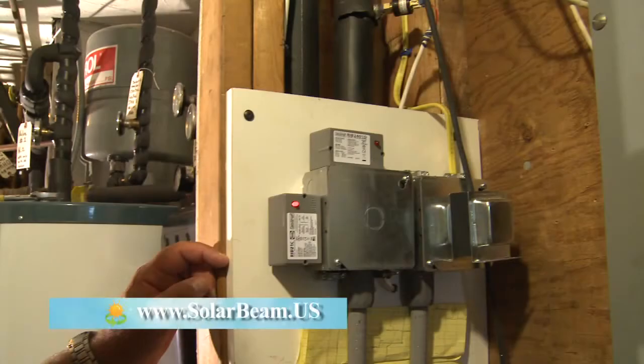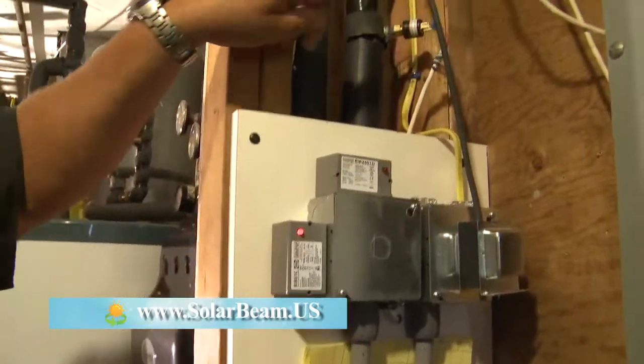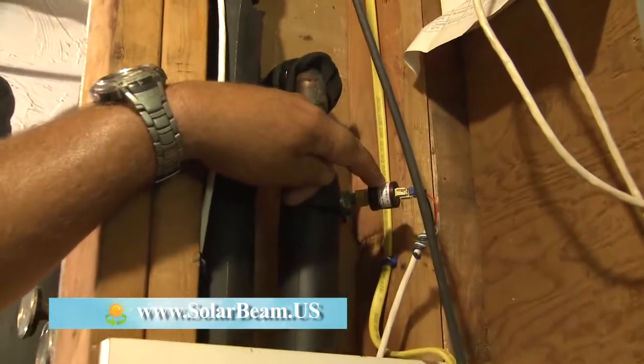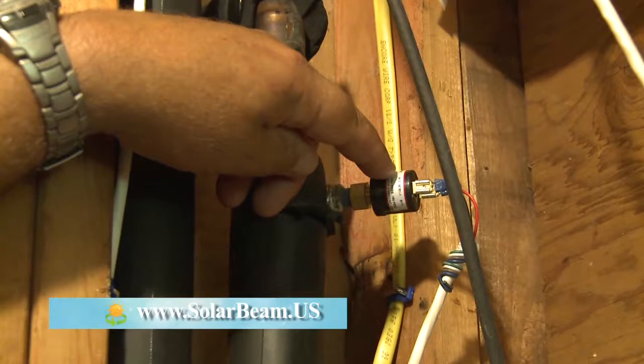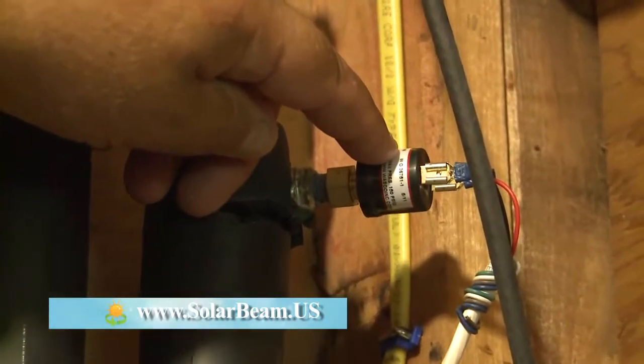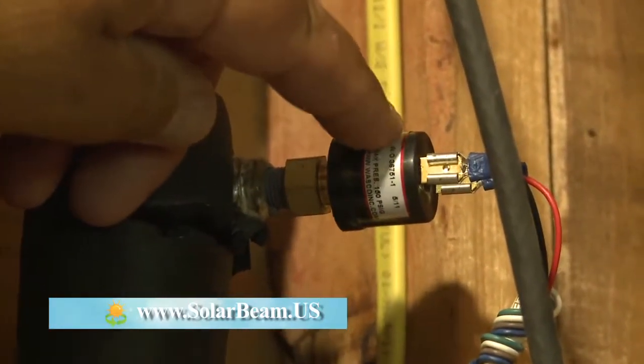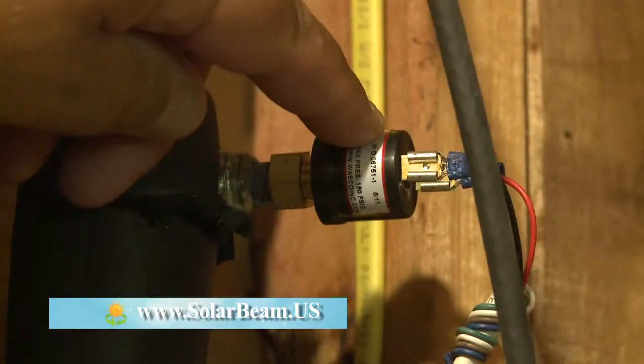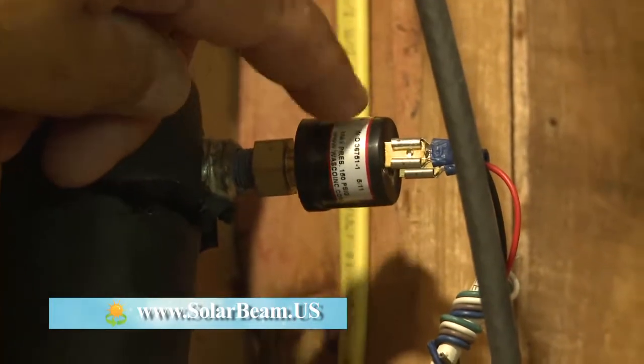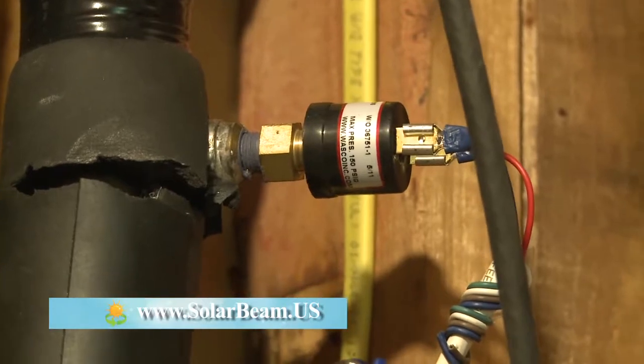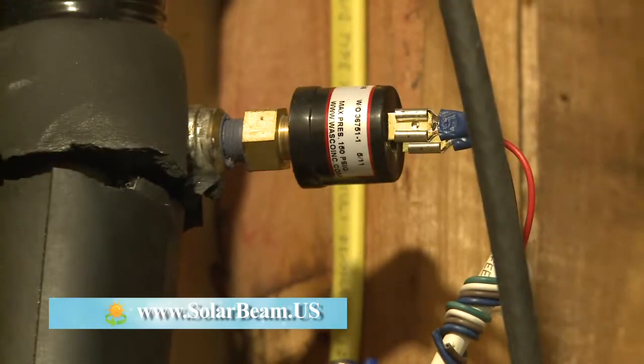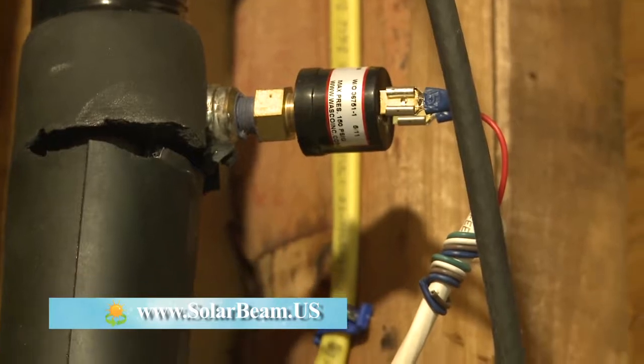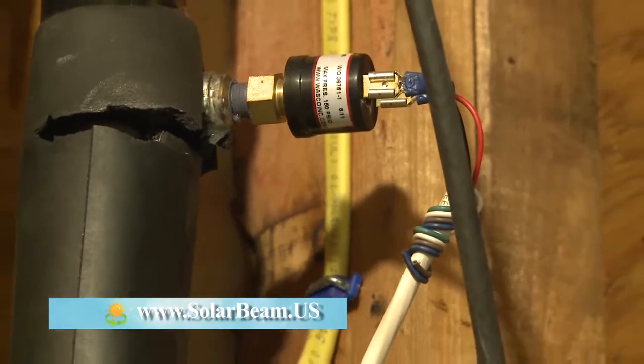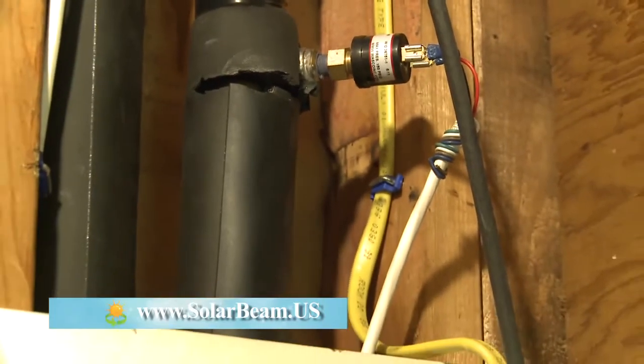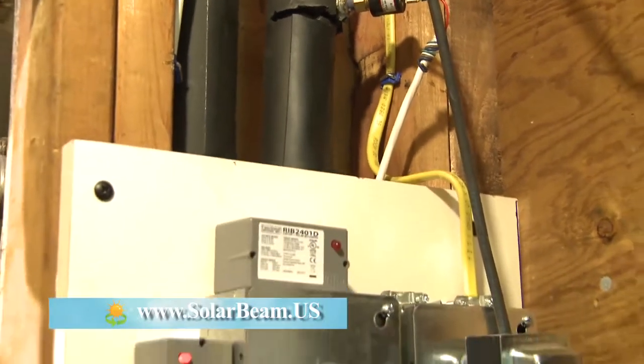There are several safety devices in the SolarBeam to prevent any type of overload or overheating. Right up in this area, this right here is a pressure switch. And if the pressure in the solar loop of the water that's going to and from the solar dish ever goes below a certain pressure, and I think it's set at 6 pounds, the SolarBeam will turn off. This is a pressure switch. We also have temperature sensors throughout the SolarBeam, so if the heat ever goes over a certain preset temperature, the SolarBeam will again shut off. There are many safety devices to prevent any type of overheating occurrence.